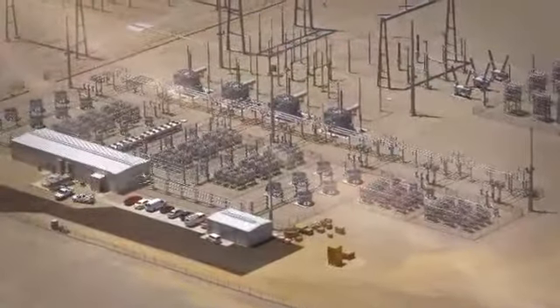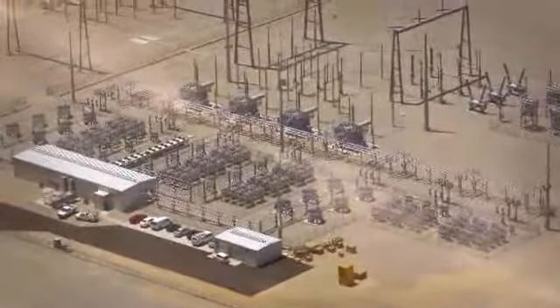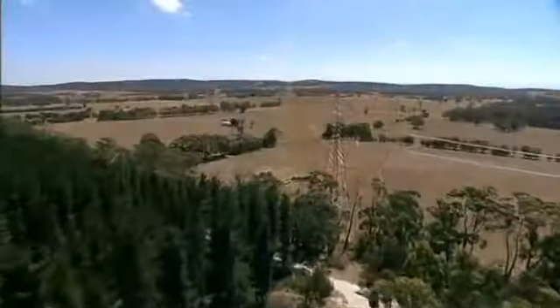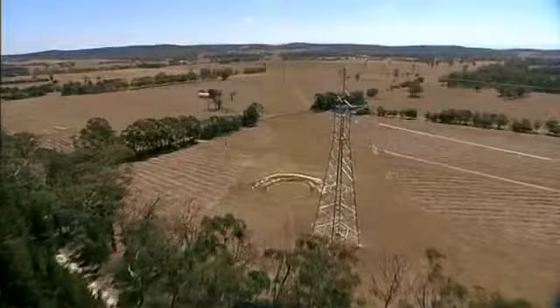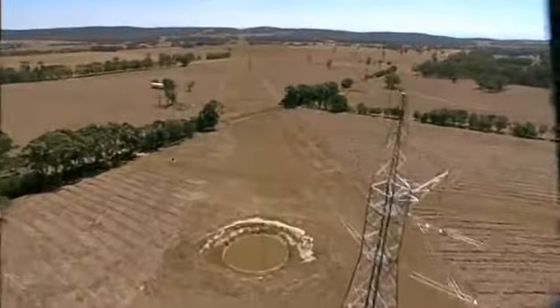Traditional electric power grids weren't built for long-distance energy transmission. They're actually regional and local systems that grew together, evolving over time. You can't simply feed 3,000 megawatts or more into your local high-voltage grid, even if you're lucky enough to have such a grid nearby. Moving large amounts of power from where it is generated to where it's needed is a problem for large-scale modern wind power projects, and HVDC systems are the solution that help get that power to market.